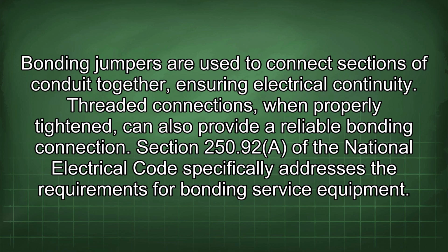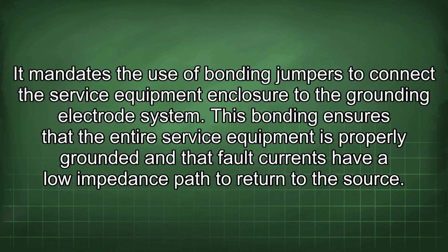Section 250.92 of the National Electrical Code specifically addresses the requirements for bonding service equipment. It mandates the use of bonding jumpers to connect the service equipment enclosure to the grounding electrode system. This bonding ensures that the entire service equipment is properly grounded and the fault currents have a low impedance path to return to the source.